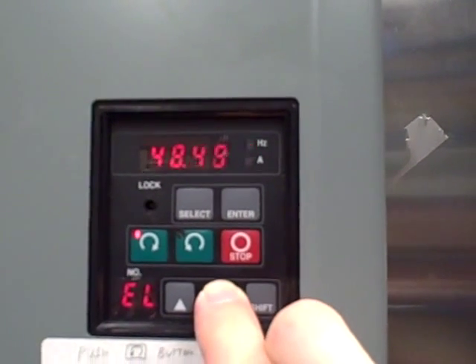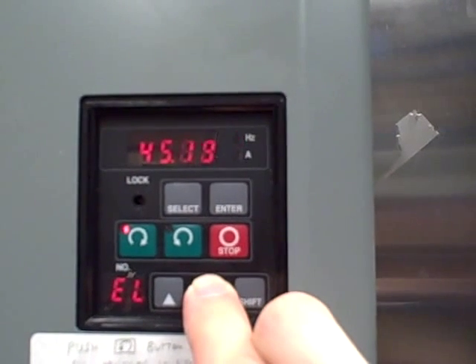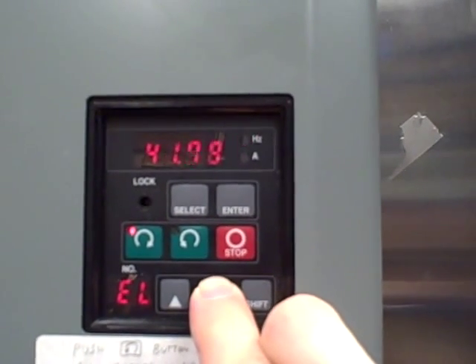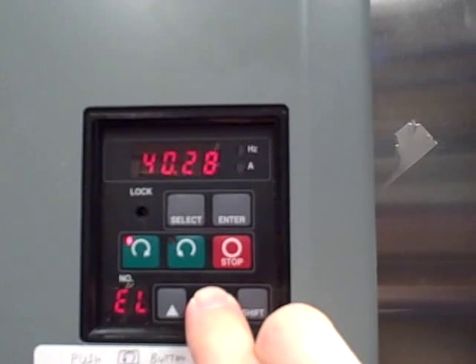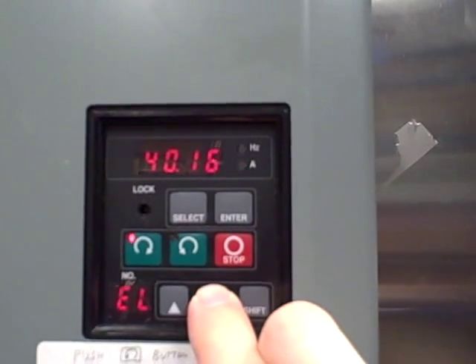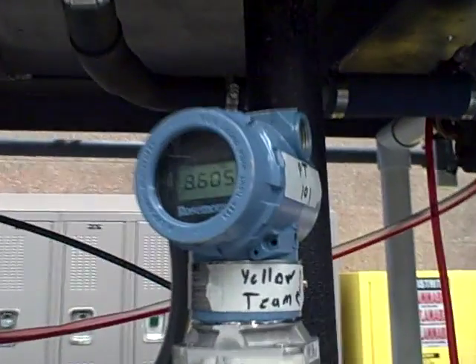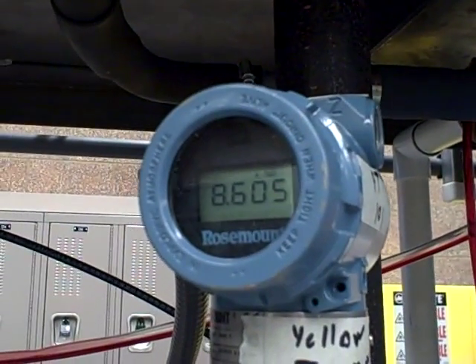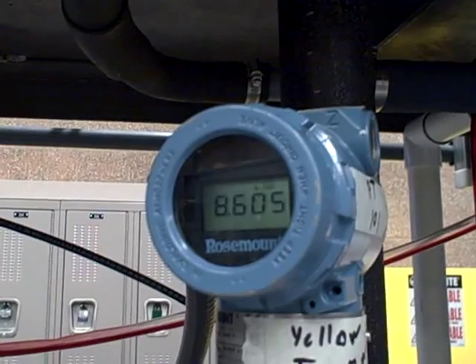You can hear the motor slowing down. There's 40 hertz. Coming over here, we read differential pressure of 8.605 inches of water column.